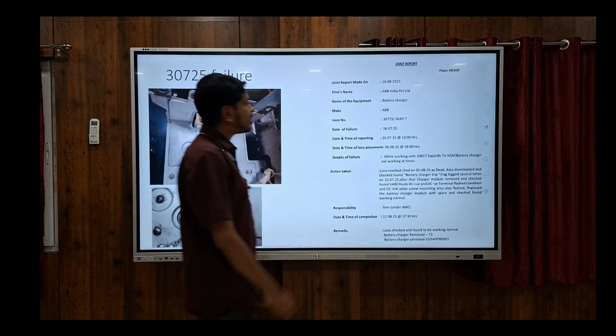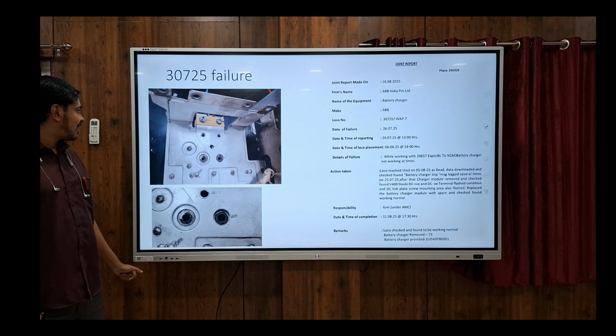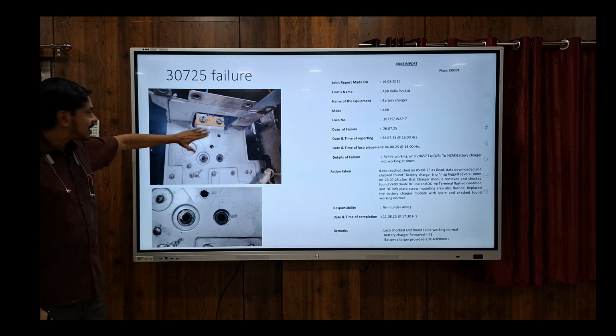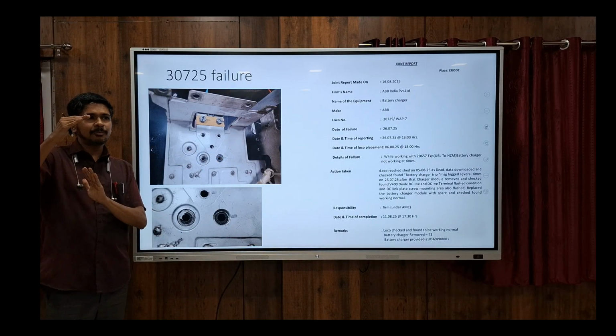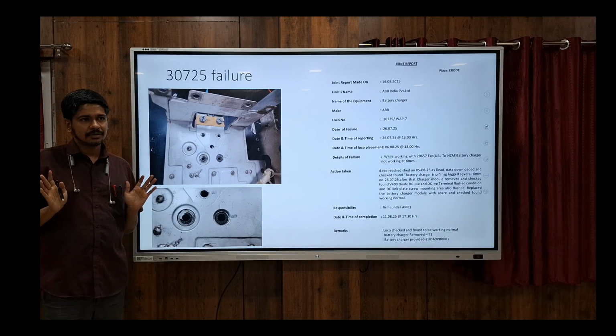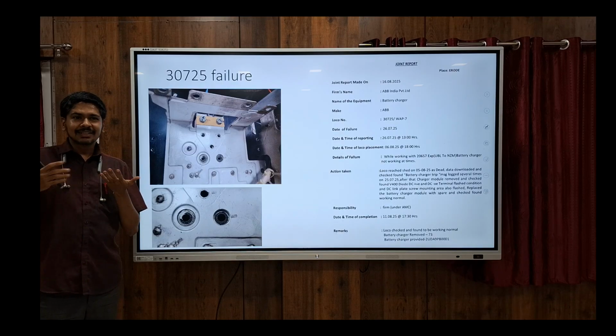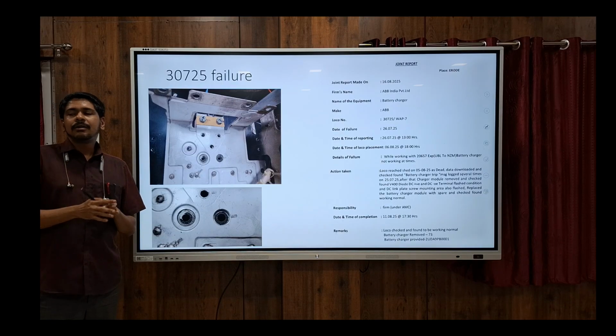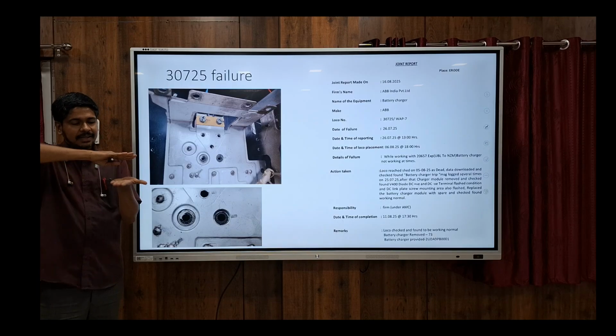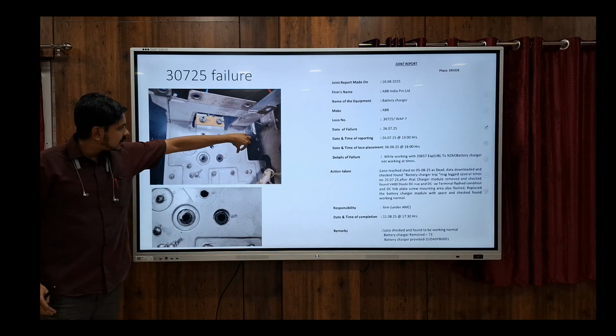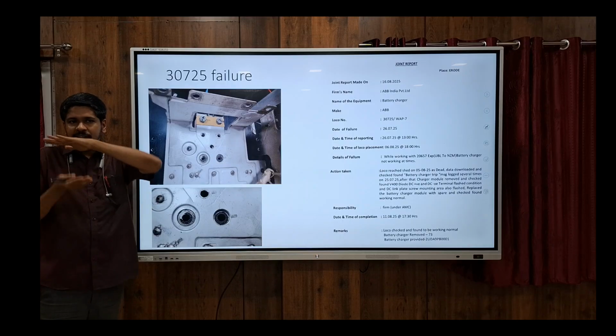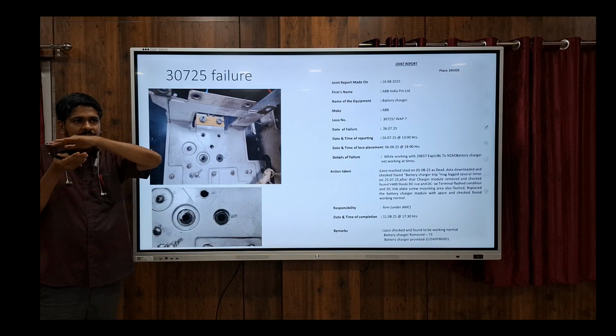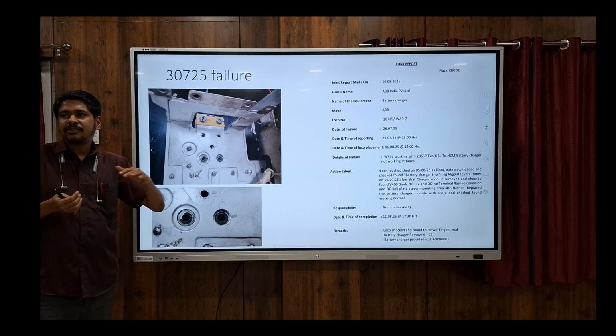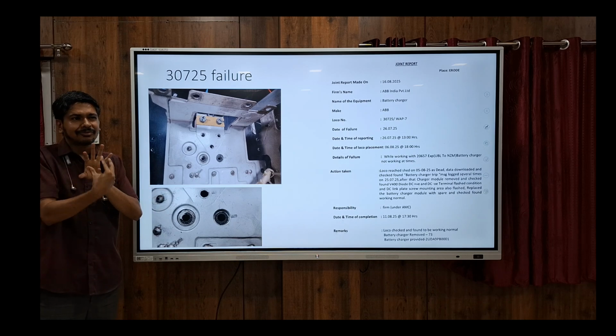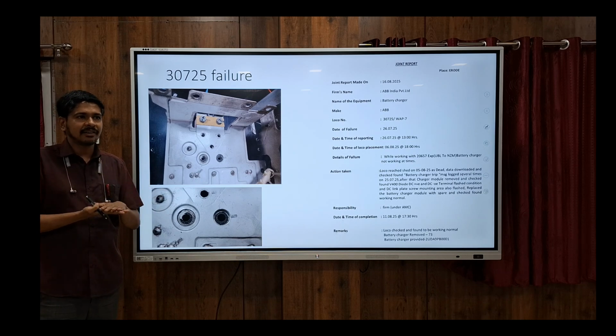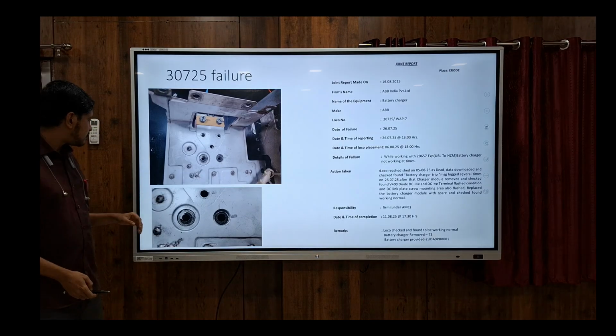And in 30725, one more case was there. There is a DC link positive plate and a negative plate. Where? After the rectifier side. These plates are insulated and separated by a minute gap, and this comes at almost the bottom side of the module, and underneath this there will be diodes, IGBTs, everything.